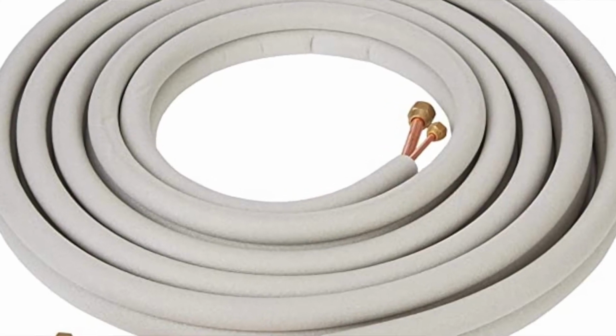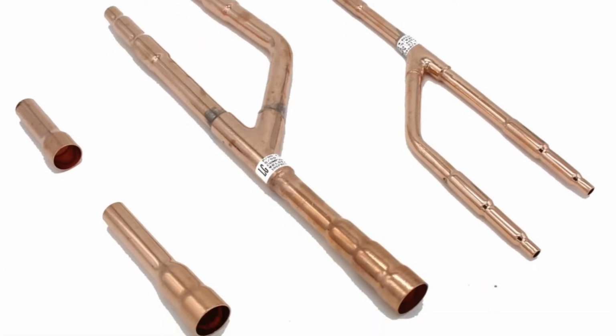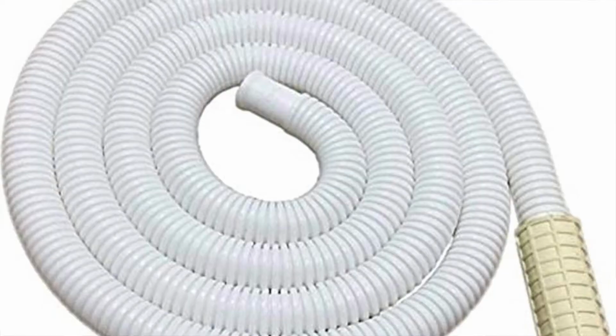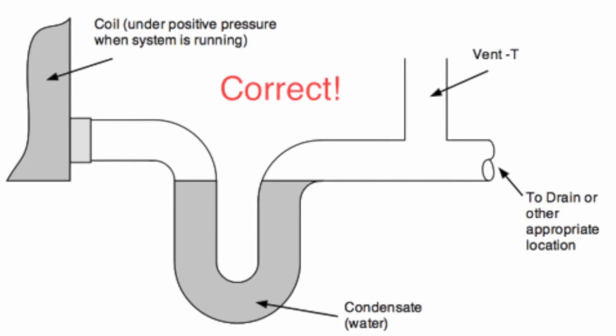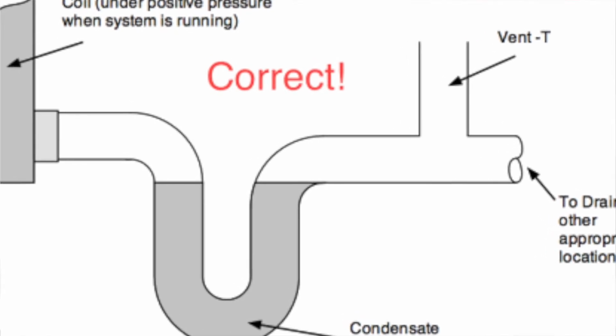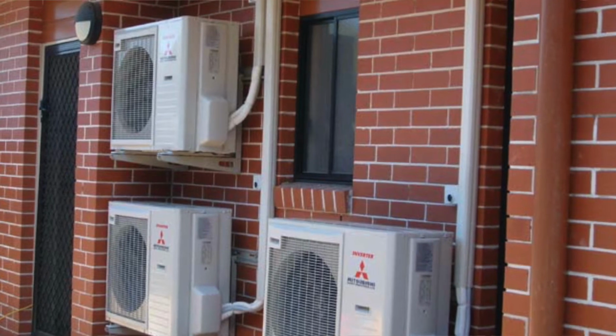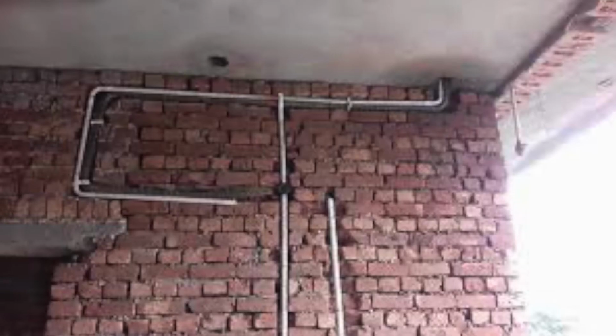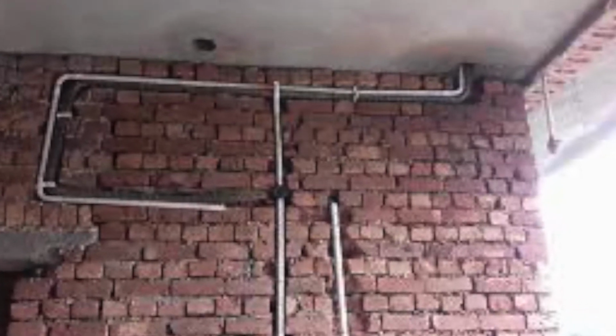Once you decide on what type of air conditioning system you're going for, the low side, or in layman's terms, the piping work, needs to be catered to. The main component of the pipe work is the copper tubes with sufficient insulation. If you're opting for a VRV or a VRF system, additional refnets are used. Another important component is the drain pipes, which drain out the excess water from the air conditioning condensation process. We need to check that these drain pipes run from the AC to the nearest drain outlet. This must be designed properly at the start of the civil process so that you can conceal the drain pipes and it is not exposed in the open.